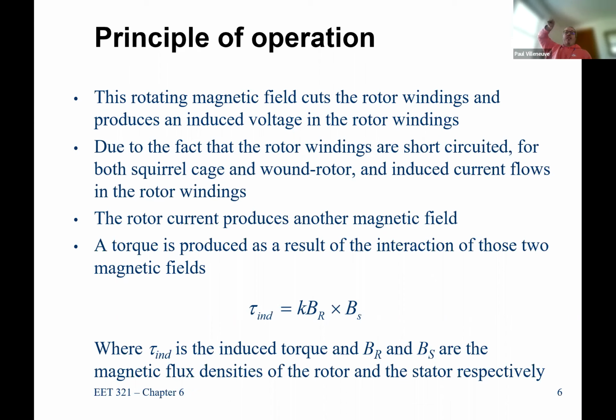Or if I'm watching something that is running at a faster speed, I can see the speed differential. So technically you can, but it's only if you use an external prime mover. But the reality of the question is any induction machine will never operate at synchronous speed, because at that point it's just a rotating hunk of metal. It's not actually operating as a motor or a generator. It's just a big piece of metal.